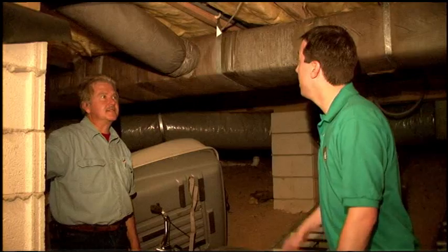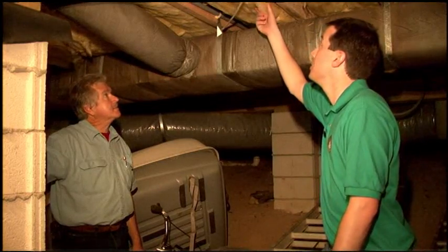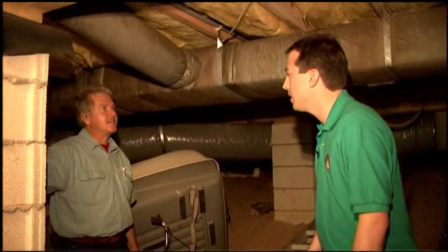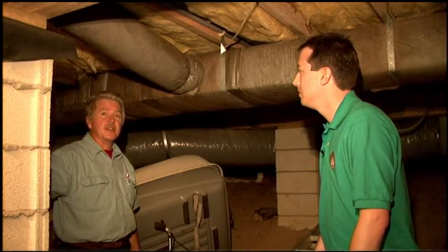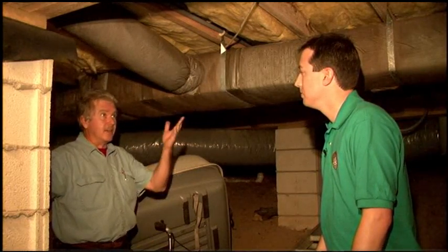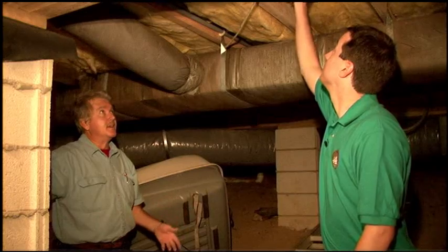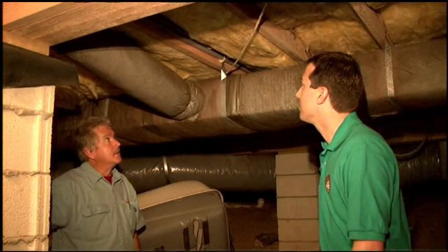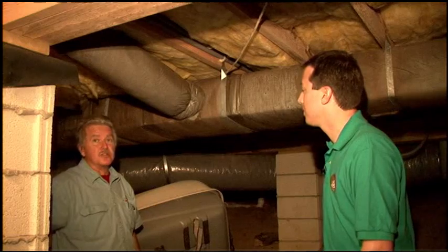So we're in the crawl space now, checking out the ductwork and the insulation. Jay, what kind of things do we want to be on the lookout for? Well, first of all, on the insulation, we want to make sure that it is actually in place and not falling down. And 2, we want to make sure it's the correct R value. And 3, we want to make sure there's no mold and mildew on it.